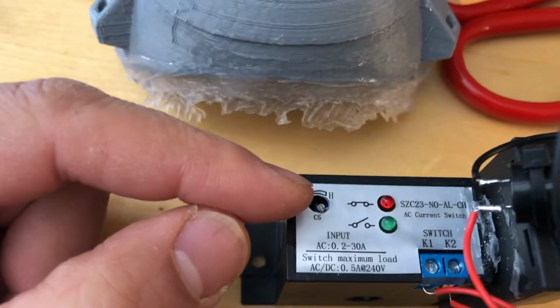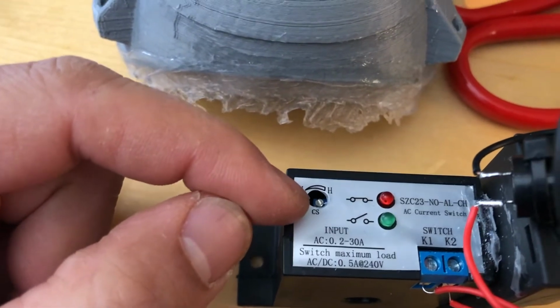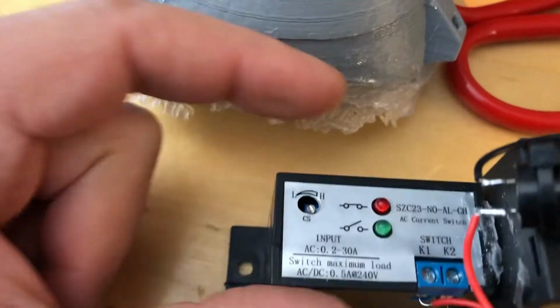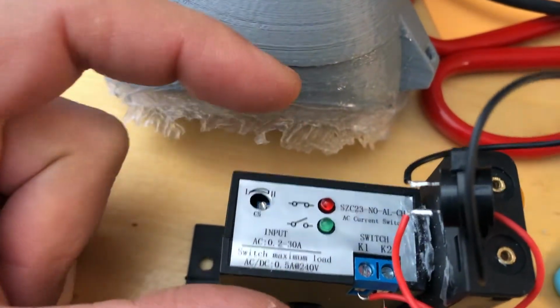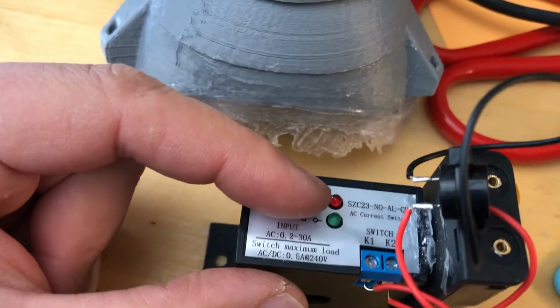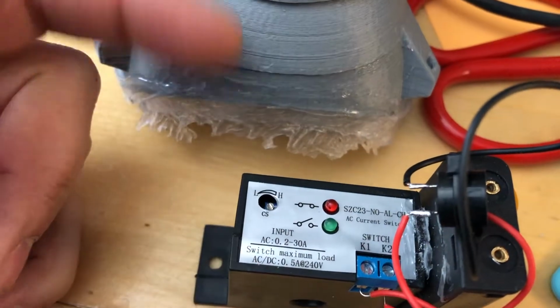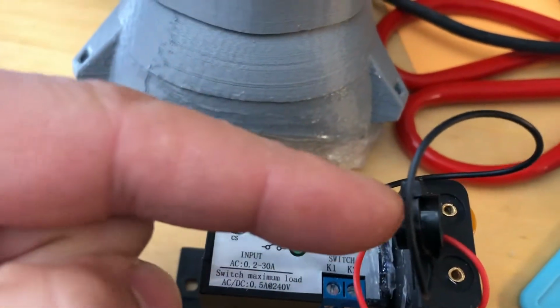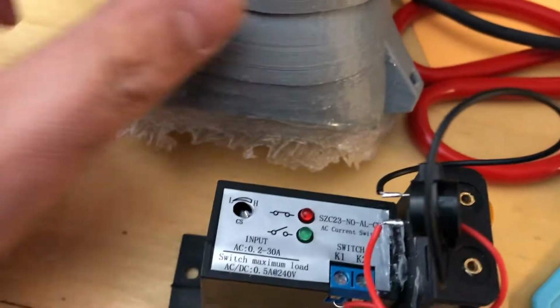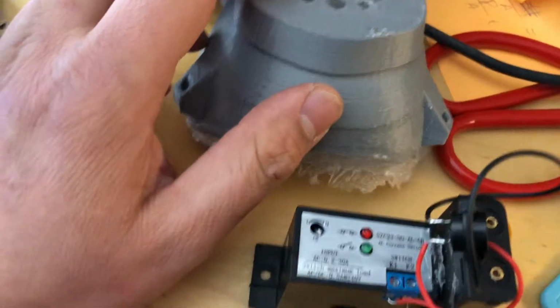I can adjust the threshold load by adjusting this trim pot right here. When it goes critical, over a certain number of amps, it switches the red light on, closes the contact inside the relay, and sounds the buzzer, meaning you've got an obstruction in your airway or something else blocking the flow of air to the patient.